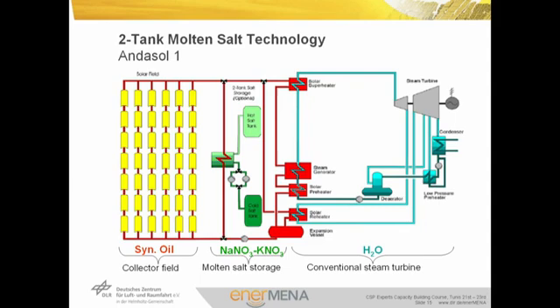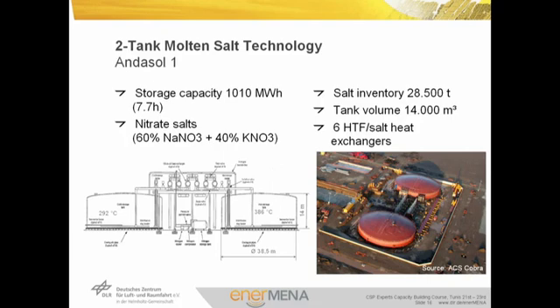An indirect molten salt storage system was first implemented at the Andasol power plants. Here, oil is used as HTF and the energy is transferred to the salt via a heat exchanger during the charging process. During discharge, the energy is transferred again from the molten salt to the thermal oil. The thermal oil is then used to generate steam. The temperature difference between hot and cold tank is in the range of about 90 degrees, so the mass-specific storage capacity is about one-third of the SOLAR2 system. This picture shows an exemplary implementation of an indirect two-tank molten salt storage system at the Andasol power plants.